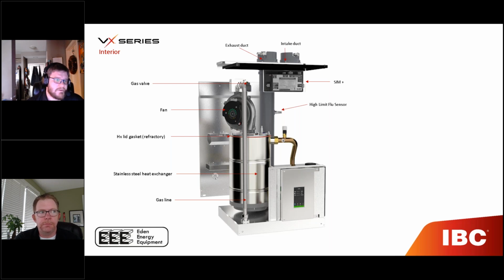If you have questions about that or if you have issues, let us know. We've got a lot of contractors who have looked at the price of CPVC versus PVC and found it's a huge savings. And it doesn't derate the boiler. It doesn't restrict the boiler to a temperature output or anything like that. The flue gas temperature sensor always continuously monitors and ensures that we are able to maintain that operation safely. Yeah, it's kind of our feature tied in.